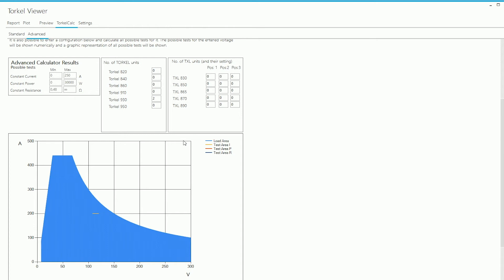The information is shown in two ways, numerically as well as in a graphical format. The blue section that you see in the graph here is the load area which covers the current capability of the configuration. So you can see that the current capability drops with an increase in the voltage. Higher the voltage rating of the battery string that I'm testing on, lower is the current capability of any configuration that I select.